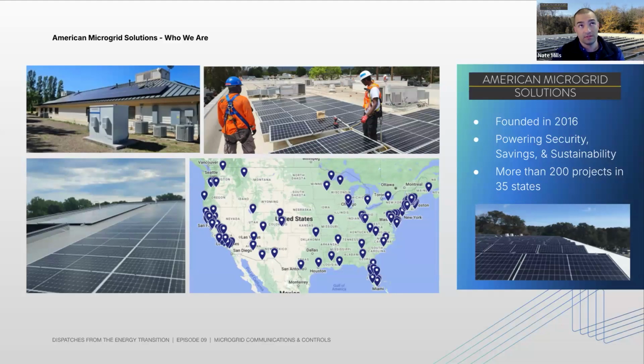Whether it's how much can we feed back into the grid and what limitations do the existing substations have? Or how do we dispatch from the batteries to either offset site load or export back to the grid to offset the demand, either just at peak times or because there is literally not enough capacity in the distribution lines. That's really what we want.